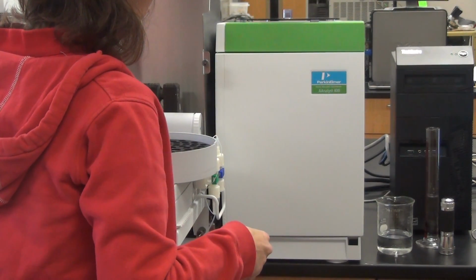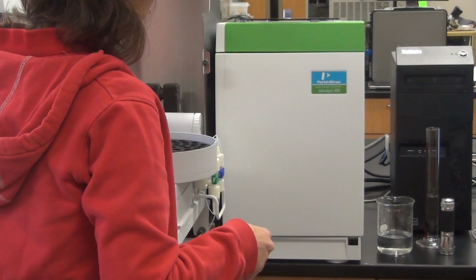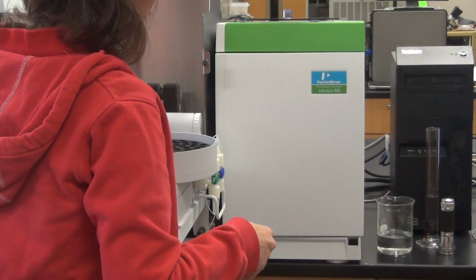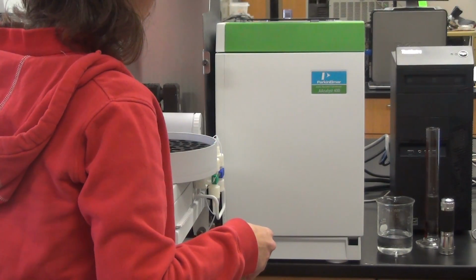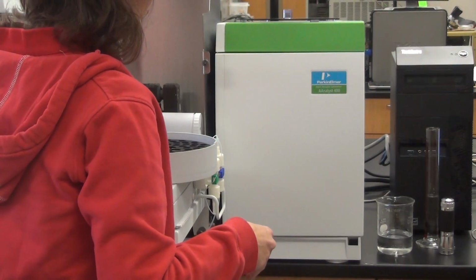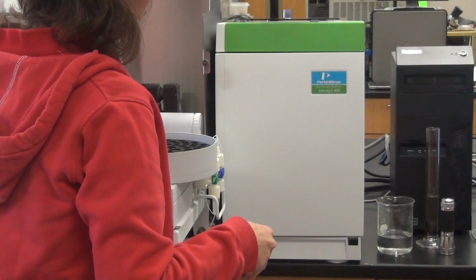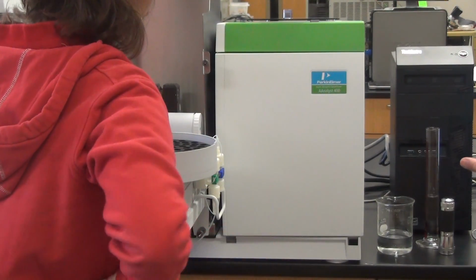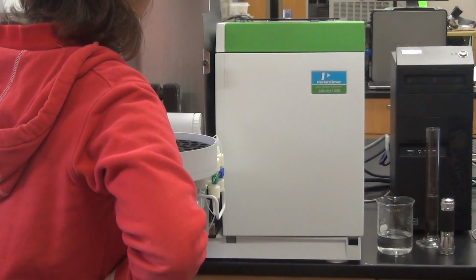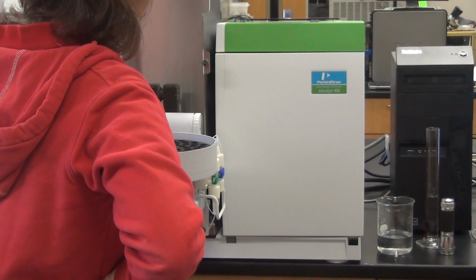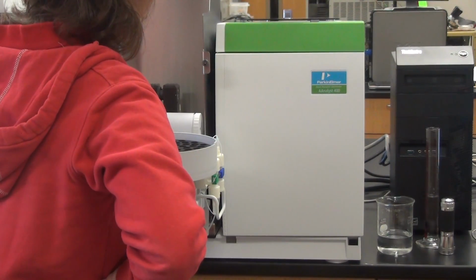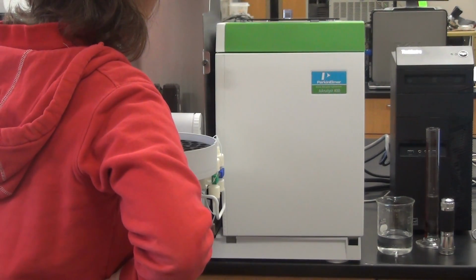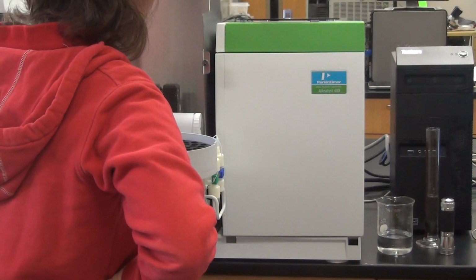And you adjust it for minimum. Then you go to the other one, adjust it for minimum. And you come back to it and adjust it, you kind of do it twice. And there'll be some lag space that doesn't make any difference, and you really want to set it in the middle. But as you can see, there's a lock on it, so it's not a touchy thing. So once you align this, it will stay aligned.